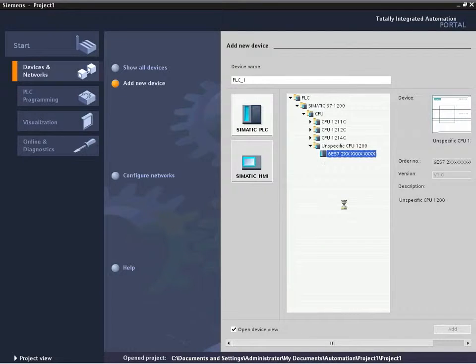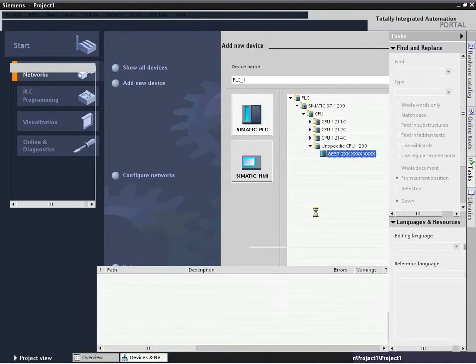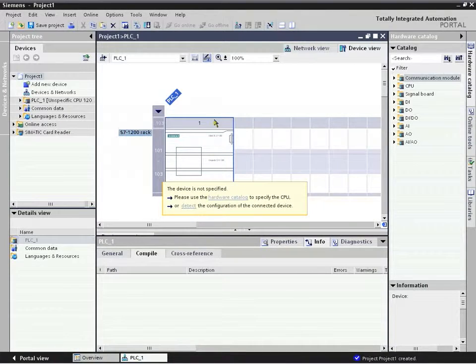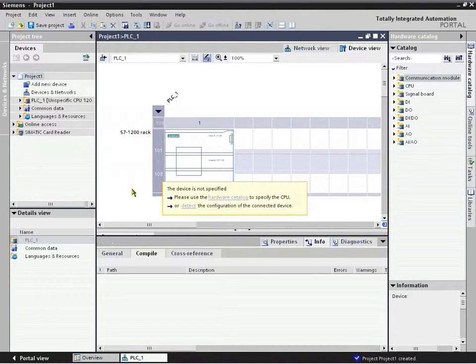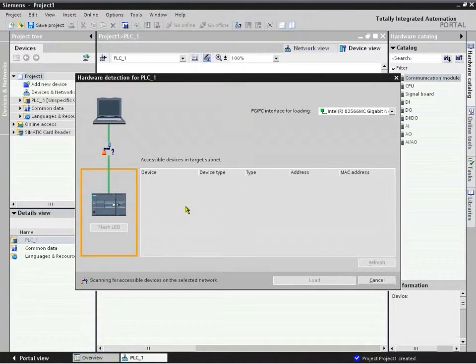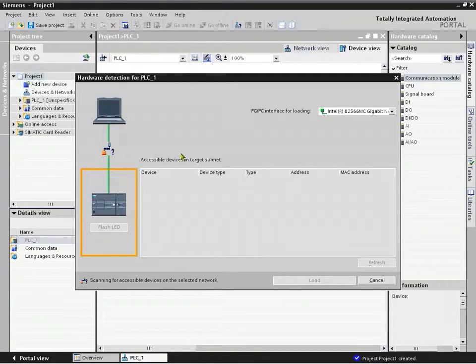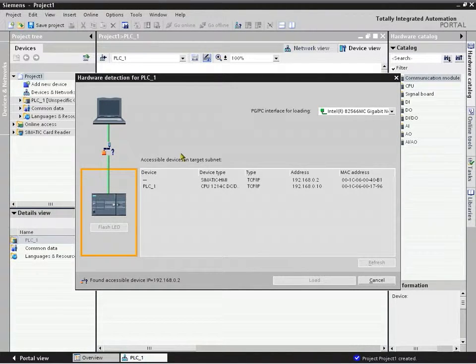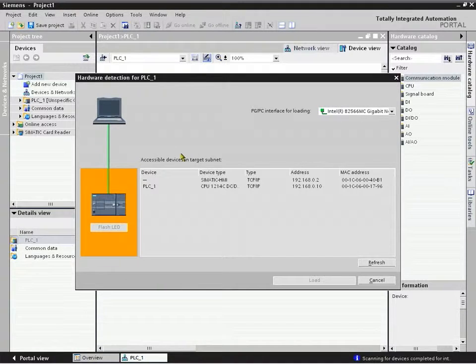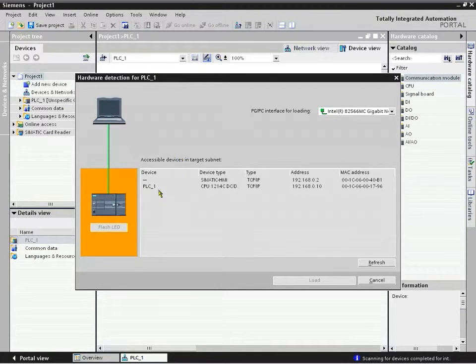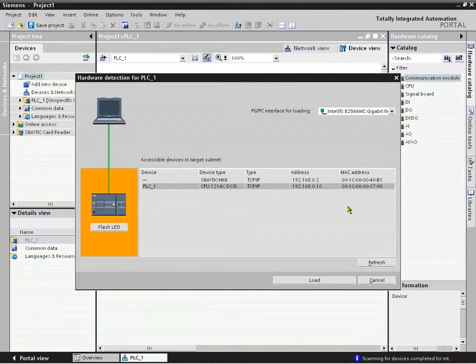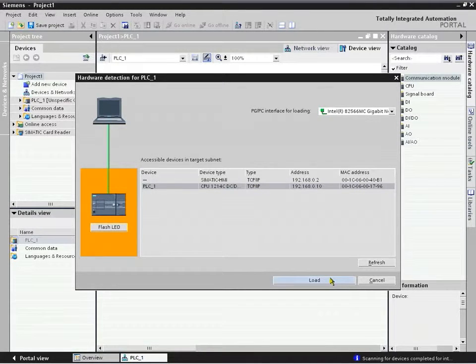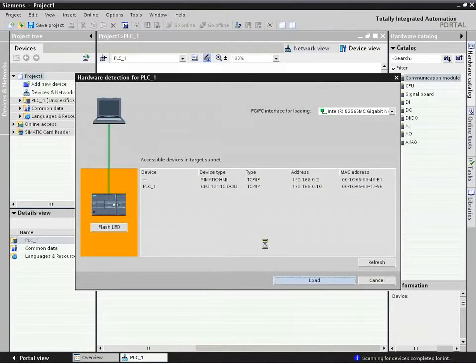And simply add that to the I/O configuration. And then proceed with the auto-detect to bring the hardware into the graphical framework that's shown here. So if we detect it, it's going out over Ethernet and it's not worried about what the IP address of the PC is that's connected to it or the IP address of the controller. It will bring anything up on the subnet of that particular LAN according to the MAC address.